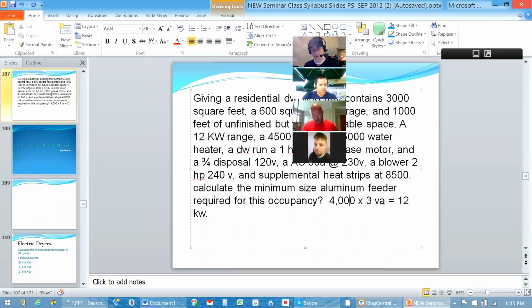And then the B section for the laundry is going to be an additional 1,500 VA minimum. So total, if you take those 3 into account, that's 4,500 volt amps, and those are mandatory code minimums that you can't exclude. Even if they tell you they want to exclude them, you can't. You're going to have those included in the standard method. So that works out to a total of 4,500 VA, and we're going to add that right here before we take our derate. We are permitted to derate that along with the lighting load. So we're going to add plus 4,500 VA here for the 3 required circuits.